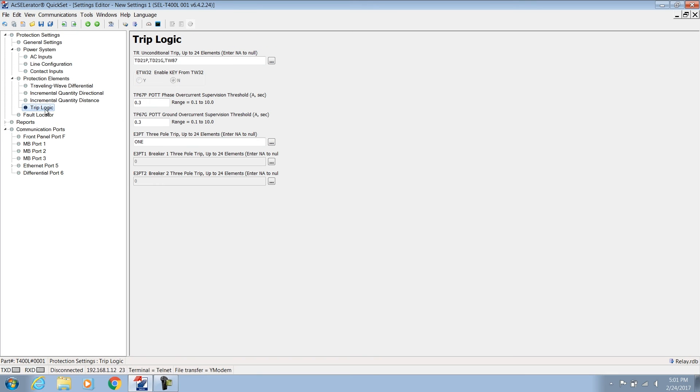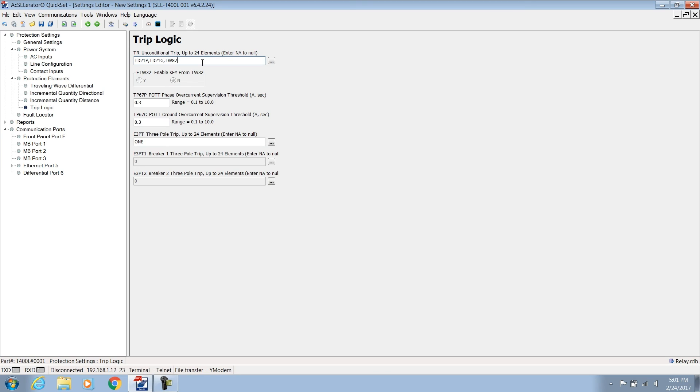The trip logic includes POTT and DTT schemes and links all the tripping and auxiliary elements together in order to control the SEL-400L's trip output. The trip logic has a few settings. TR is a list of elements used for tripping unconditionally. We intend to use the TD21 and the TW87, so we list the TD21P, the TD21G, and the TW87 as the tripping elements.